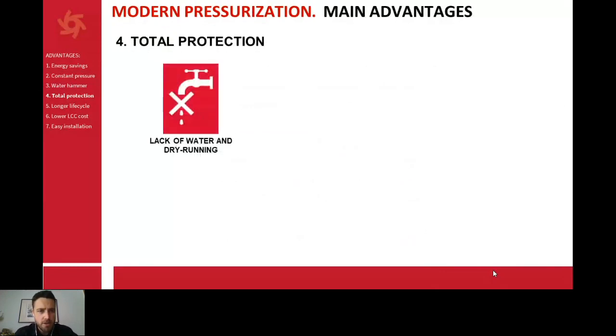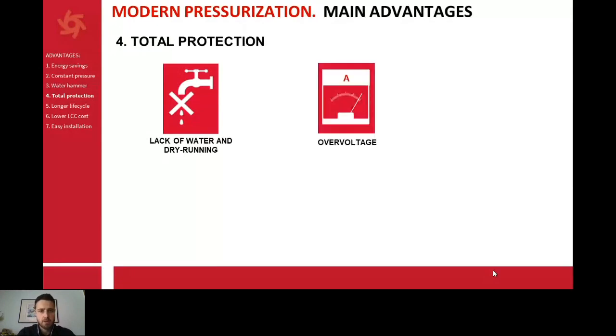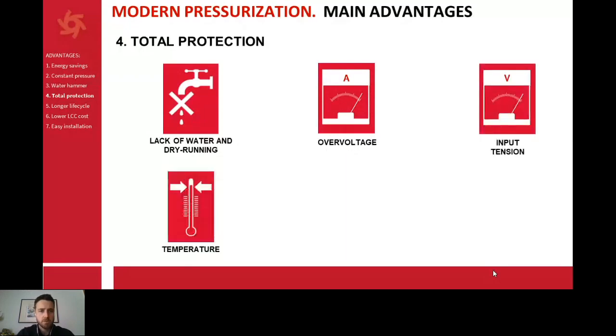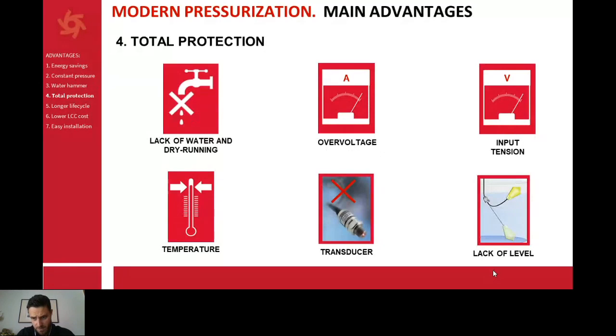Which are the protections that we have with these booster sets? Total protection against lack of water and dry running. In case we don't have any water or any pressure in the pipes, thanks to the transducer or the pressure sensor, we will notice and we will stop the pump, so it will not damage the pump. Overvoltage, input tension, temperature. In case of high temperature, the speed drive will stop the system. If we do not have a transducer, it will stop, or the second pressure sensor will start. And in case of lack of level, the system will also stop.